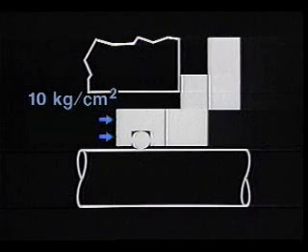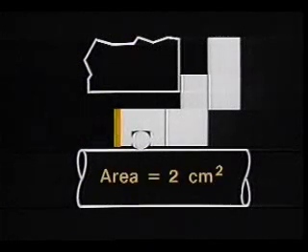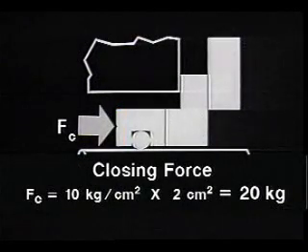For example, let us assume that we have 10 kilograms per centimeter squared of pressure in the stuffing box. This pressure is generating an axial force on the back of the rotary. This area is 2 square centimeters. Thus, the resulting closing force from this condition is 20 kilograms.